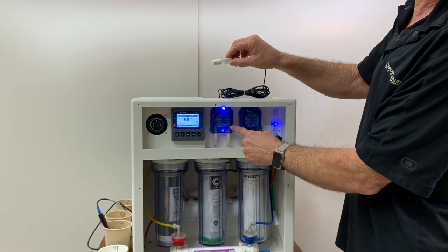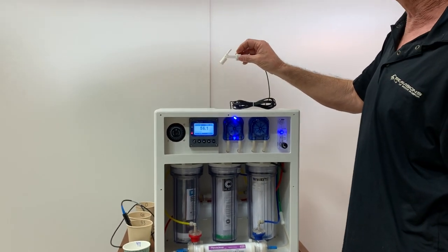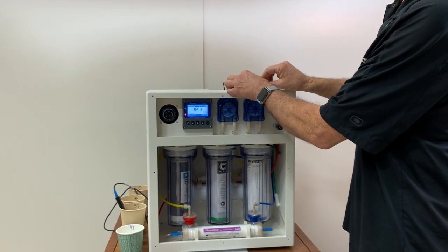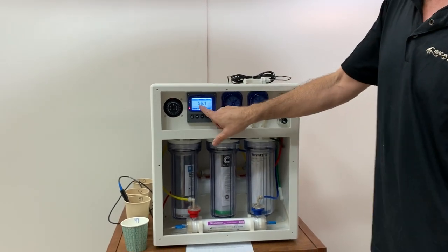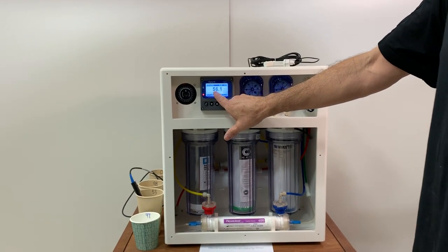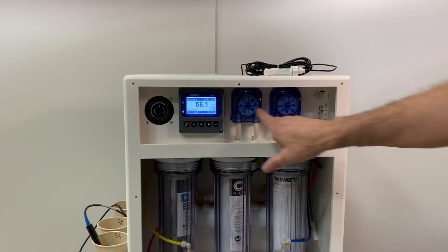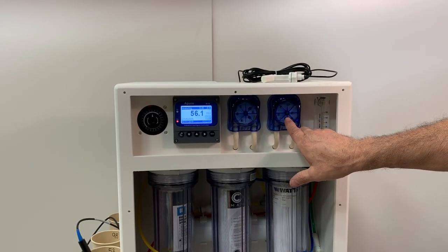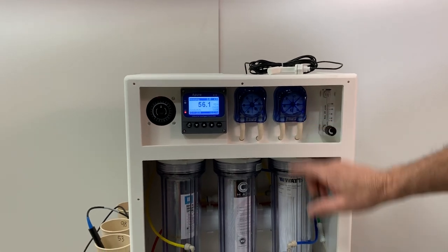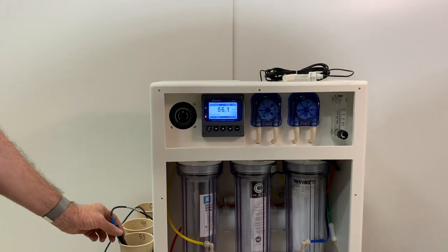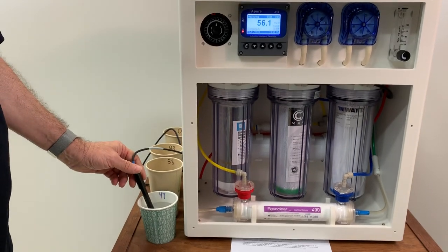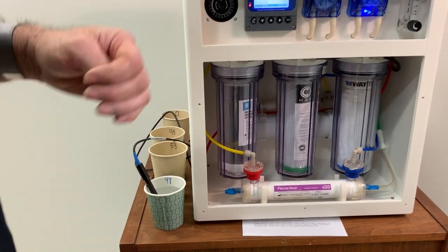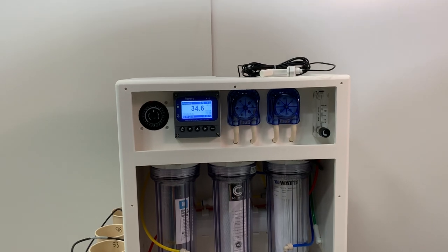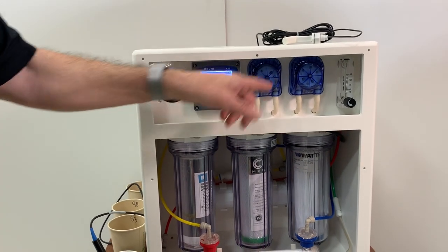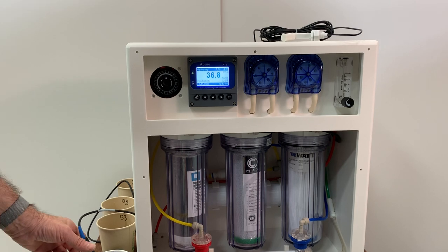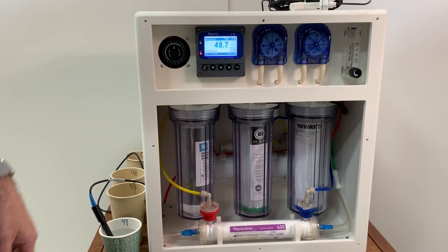I'm going to turn this pump off for now by just lowering that float switch. So right now we're at a value that is higher than the set point that I want to keep my salt. So the salinity, so the salt pump is not activated. If I were to take the probe out and put it in a solution that's below, you'll see, no, actually what it did is it just went so far below it put the machine in alarm. So it'll have to come back up again a little bit.